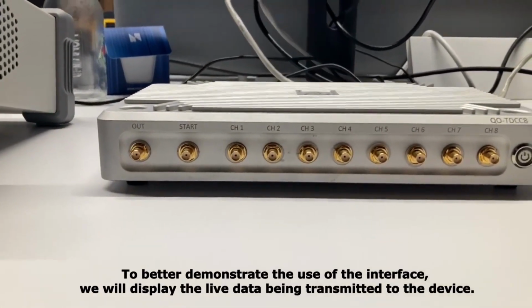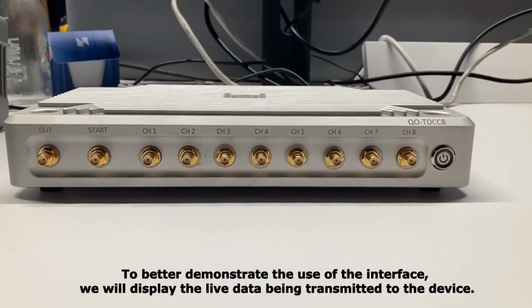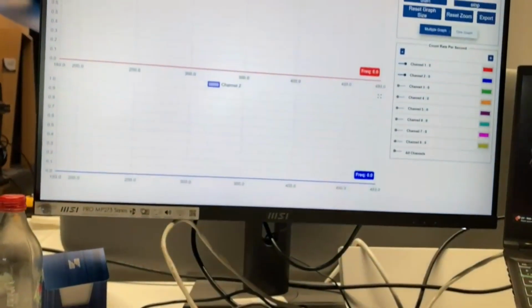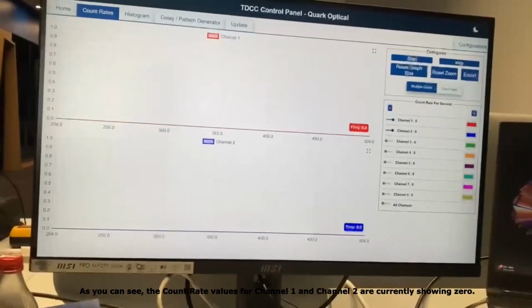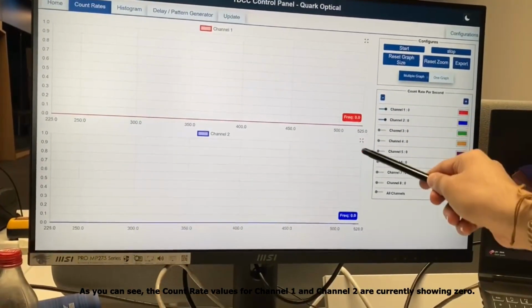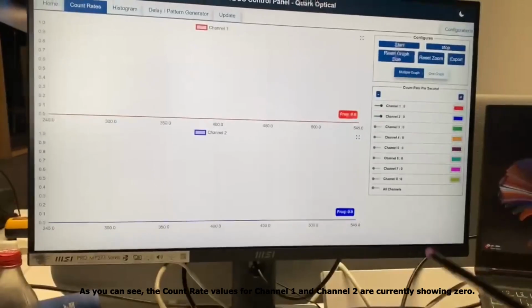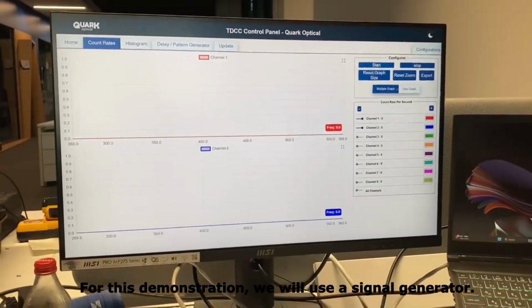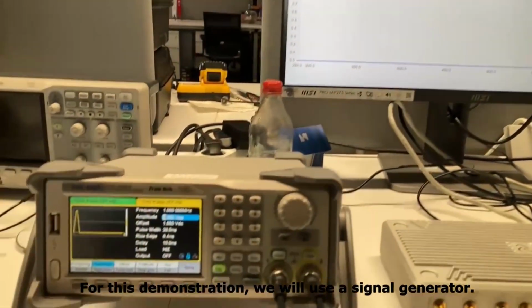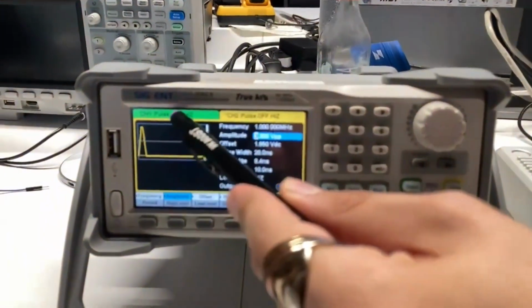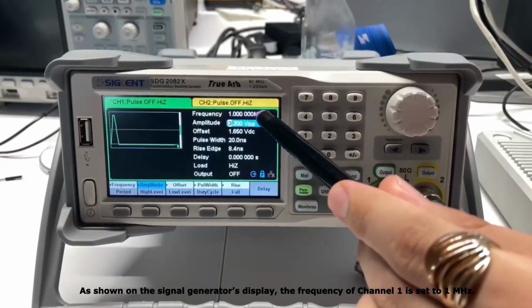To better demonstrate the use of the interface, we will display the live data being transmitted to the device. As you can see, the count rate values for Channel 1 and Channel 2 are currently showing 0. For this demonstration, we will use a signal generator. As shown on the signal generator's display, the frequency of Channel 1 is set to 1 MHz.